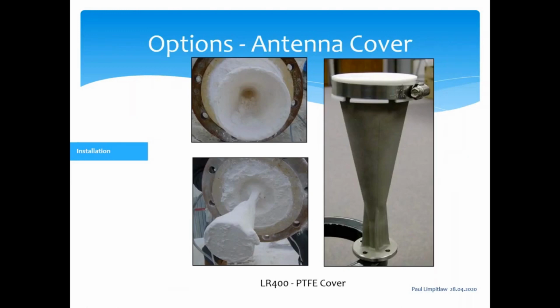A couple things to point out that might make sense as options, specifically in solids applications: certain solids can coat or build up on the horn of your radar or transducer, specifically in a high humidity, high moisture environment. So we offer a Teflon cover for a radar transmitter. Teflon has a very low dielectric, so the radar waves go right through that Teflon face the same way you or I would look through a window and not see the glass. This is one way we can mitigate buildup, as you see in those two pictures.